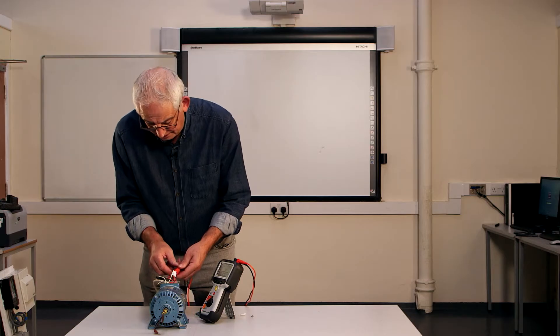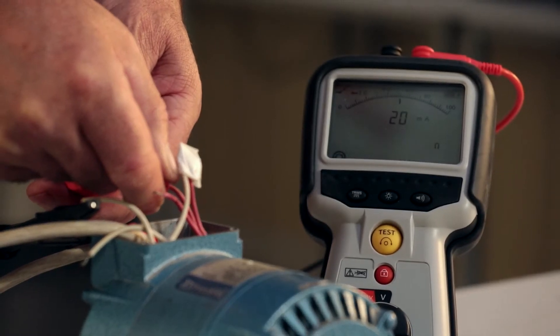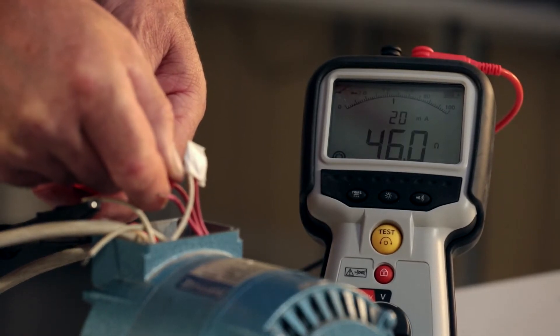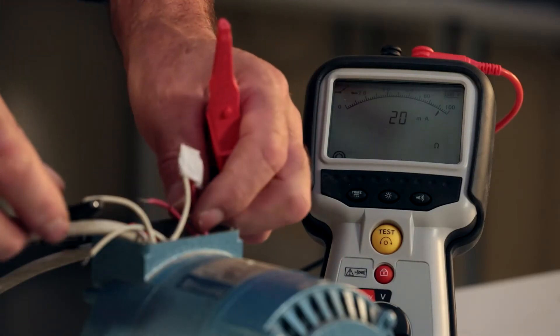Next, choose another winding. I'll persevere. There we go. And then check again. 20 ohms again, so that's the same as the other pair. Perfectly okay.